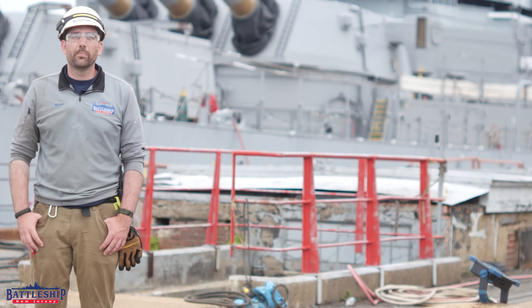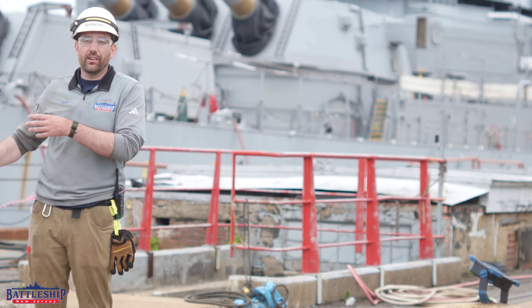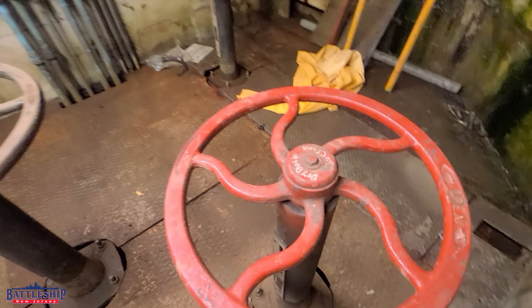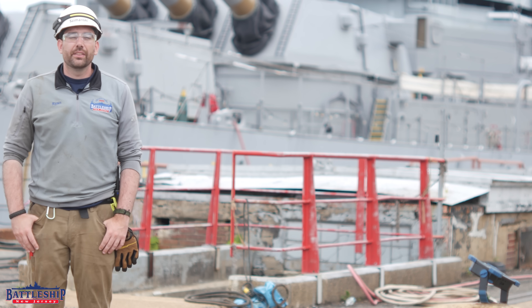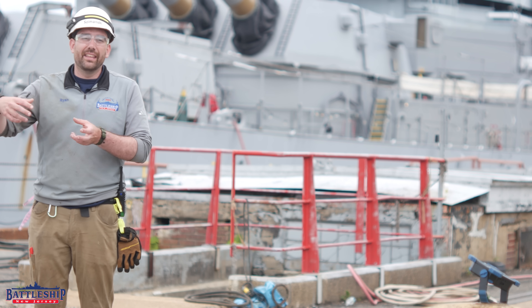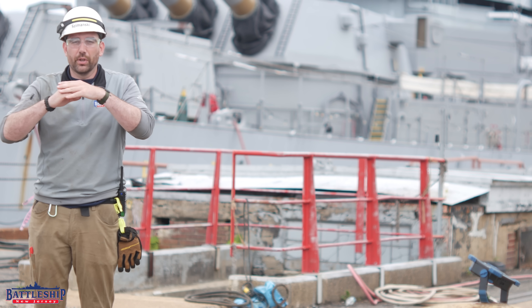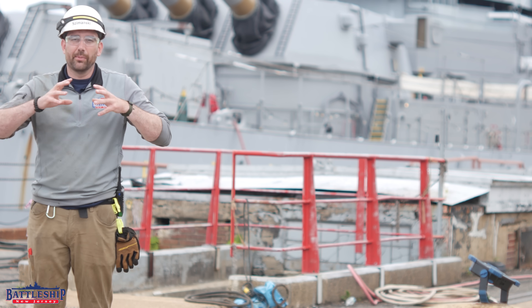Down there is also the lower part of the large ball valve that you open — that lets the pipe connecting that area to the river open up. You have to open a valve to let water into that space to start flooding it so that the pump impellers are actually in the water and not air bound. Then you have to open this other valve to have somewhere to force that water to. These valves are all opened from higher platforms with big handles connected by shafts down to the actual valves themselves — gate valves in the lower section that are threaded. As you're spinning it, it's basically opening up a gate in the opening. If you want to open it all the way, you can pull the gate all the way up; if you don't want that much, you can leave it partially open.